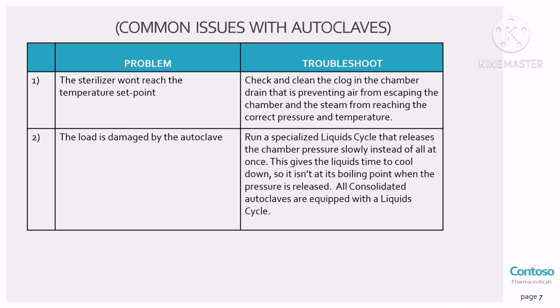Common issues with autoclave. The problem: the sterilizer won't reach the temperature set point, so you must check and clean the clog in the chamber that is preventing air from escaping the chamber and the steam from reaching the correct pressure and temperature. 2. The liquid is damaged by the autoclave, so you must run a specialized liquid cycle that releases the chamber pressure slowly instead of all at once. This gives the liquid time to cool down, so it isn't at its boiling point when the pressure is released. All consolidated autoclaves are equipped with a liquid cycle.